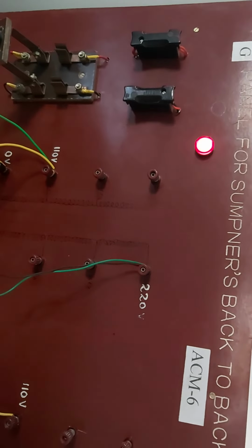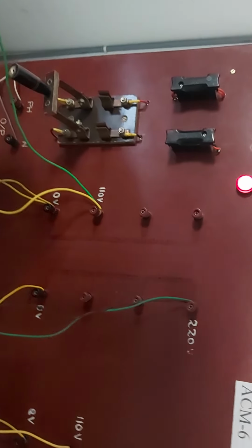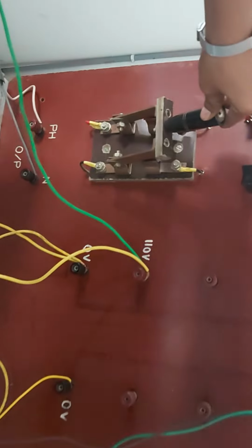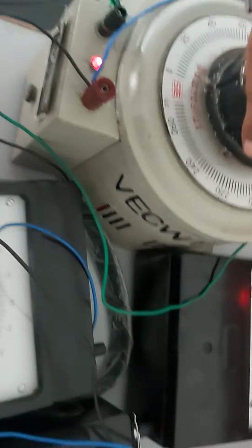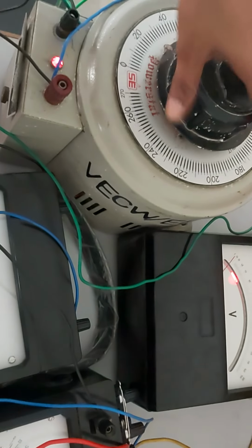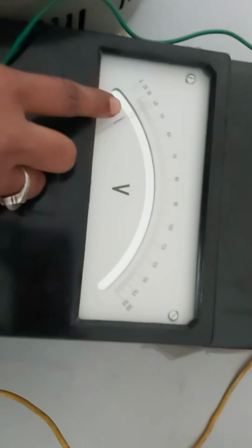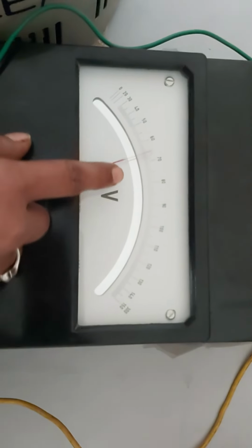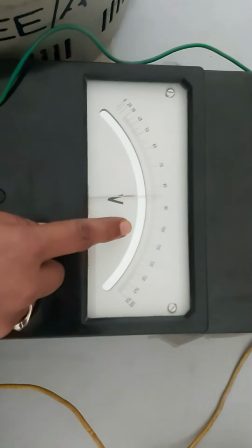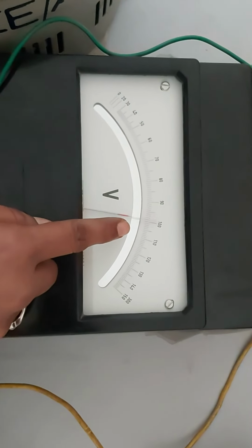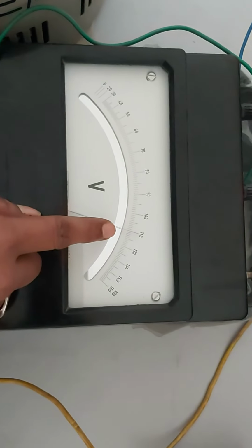Now we are going to start the experiment of Sumpner's test. Here the main is already switched on, and from the main we are getting the supply to the single phase variac. First we have to close the DPST switch. After closing the DPST switch, we have to vary the variac up to the rated voltage of 110 volts for transformer 1. You can observe the voltage in the voltmeter as you vary the variac. Slowly increase the voltage up to 110 volts.